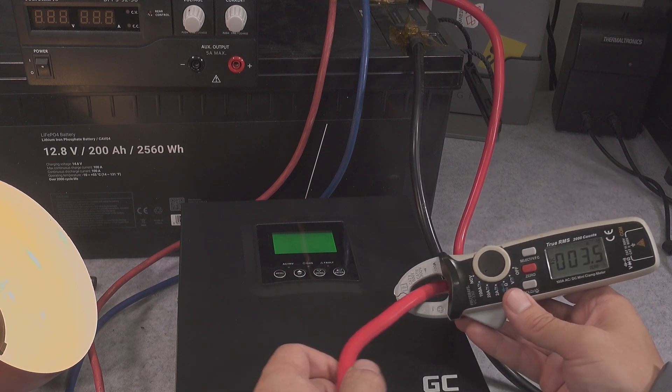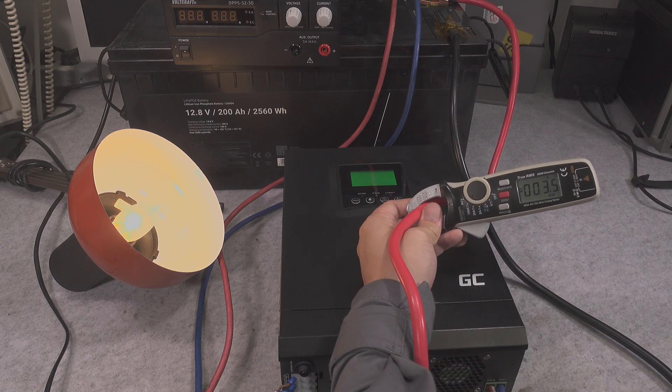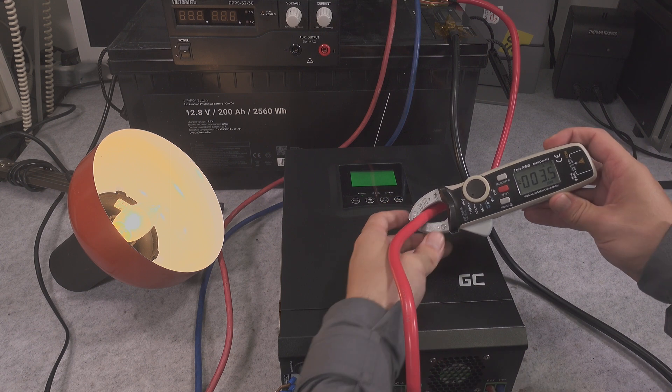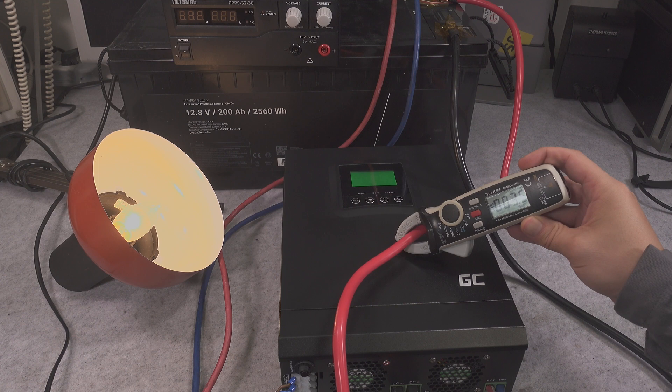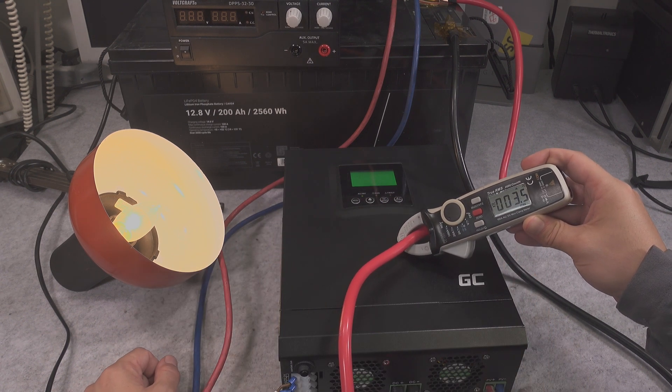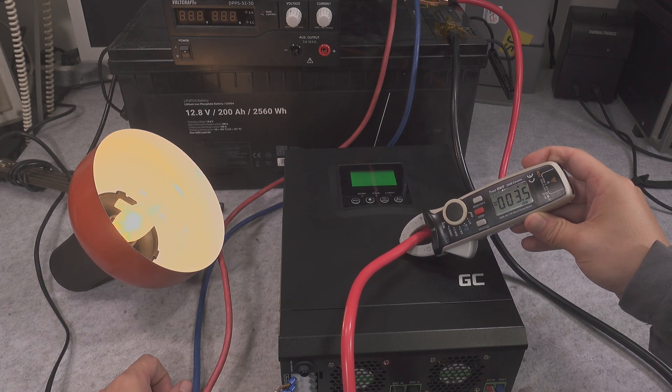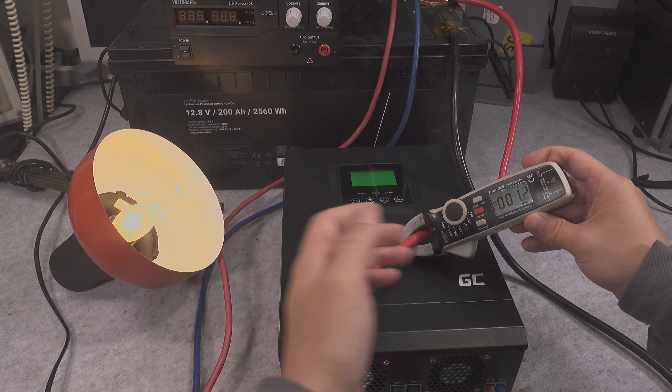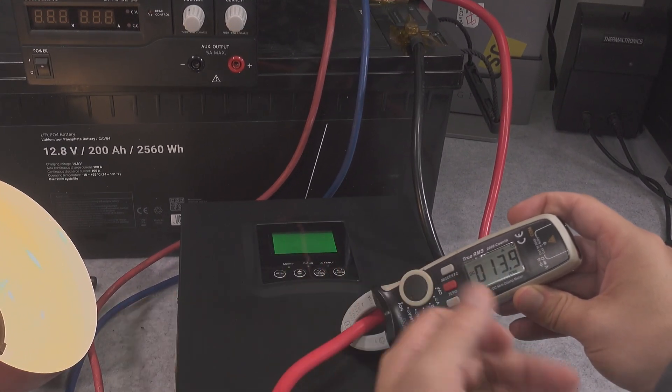It's working absolutely beautiful. In case the grid came in, we can repeat our test. It should be detected in a moment and we are going to be nicely transferred to the grid. Everything is working as it should be. We hear the click and we are going to be recharging. As you can see, we are sending current into the battery, absolutely beautiful.